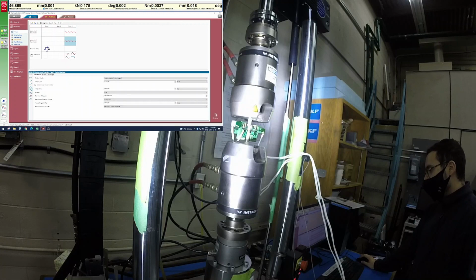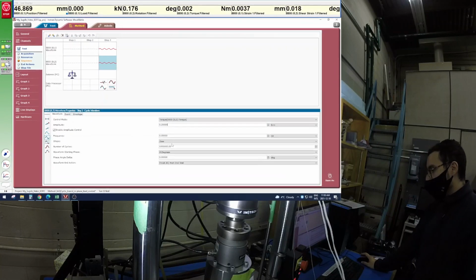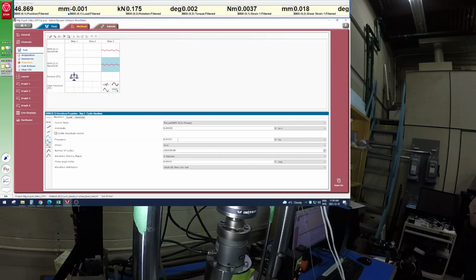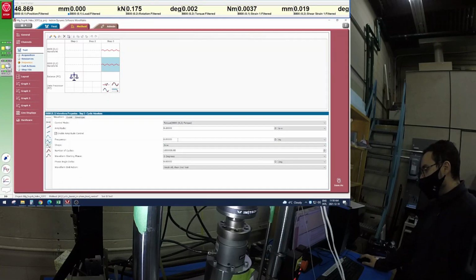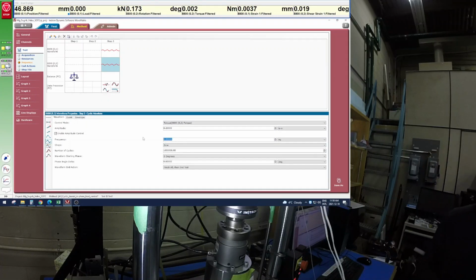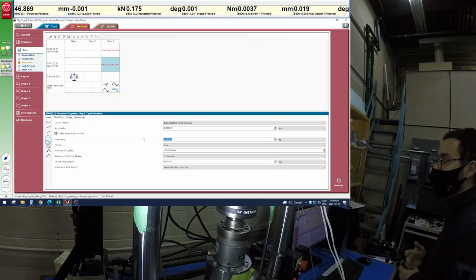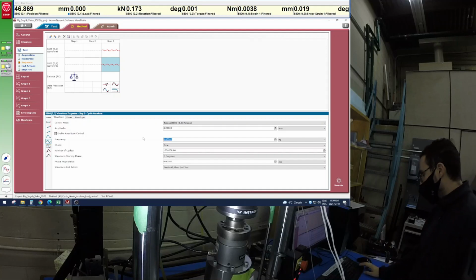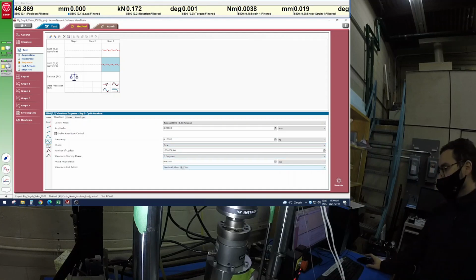And now we can go to the second waveform, which is torque, and we want to go between 0.2 plus or minus Newton meters, and we're going to make sure that you have the same frequency here. It's very rare that you want to have different frequencies, because obviously you're going to have kind of variable amplitude loading. Then it's not going to be a cyclic thing, and things will be out of phase all the time. So we want to make sure that we go to 0.1 here, sinusoidal again, 0 degree of offset.